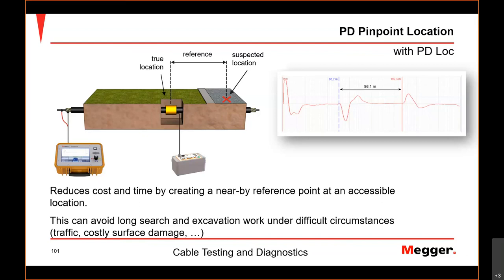Can the PD diagnostic system replace the IEC recommended procedure for testing, in particular the HV test for 1 hour, for the newly installed cables, or should it be complementary only? It could replace, well, it could shorten the duration. If you do a voltage withstand diagnostic, you could reduce the time. Imagine you do, according to the standard, the VLF test. That's supposed to be 1 hour.